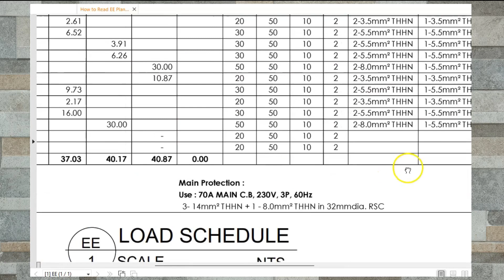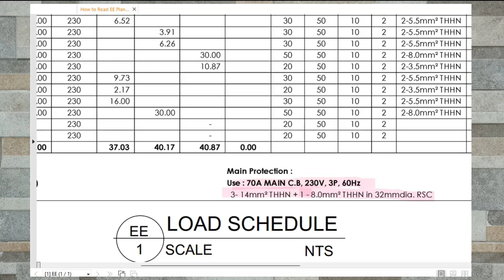And then yung ating main protection or yung ating panel board. So, if mabasa mo to, if makita mo to, ito yung ating main circuit breaker ng ating panel board. So, meron tayong 70 amperes, 230 volts circuit breaker, 3 phase, 60 Hz. So, yung main wire natin is tatlong 14 square mm THHN, isang 8.0 saka 32 square mm na RSC. If i-reflect natin sa single line diagram, the same lang dapat sila.